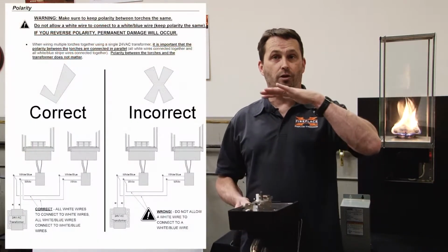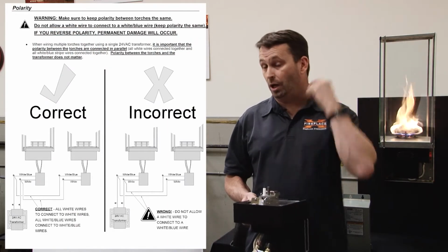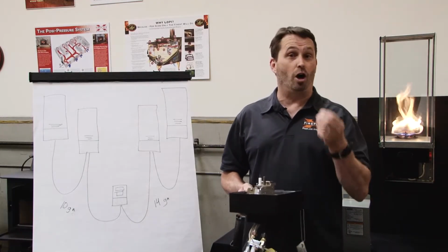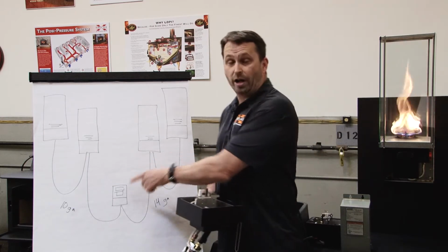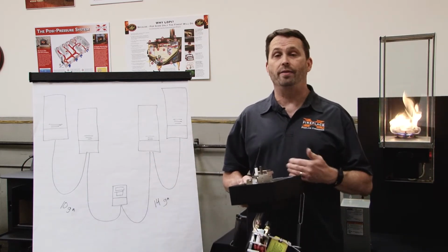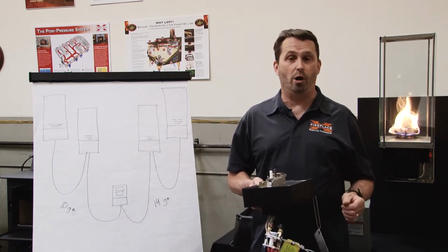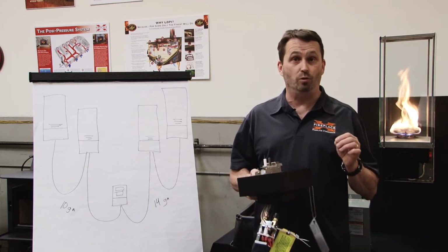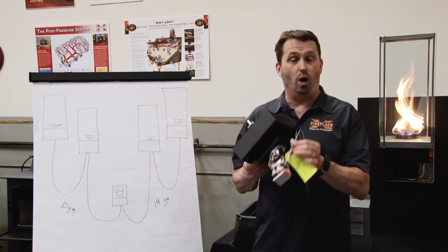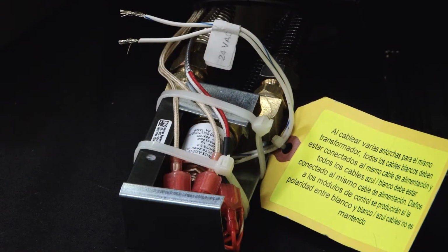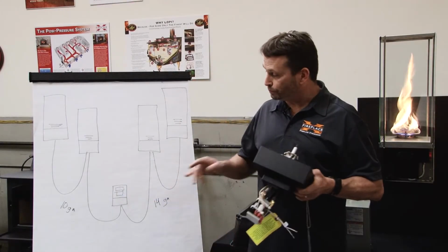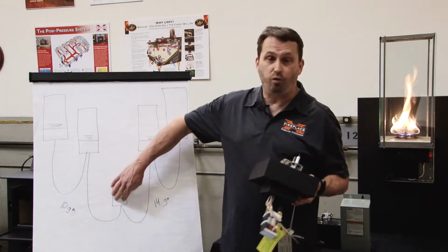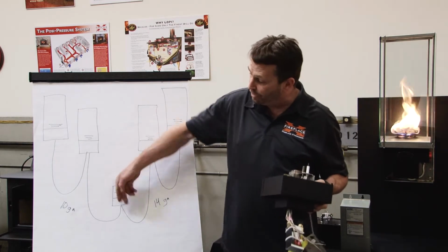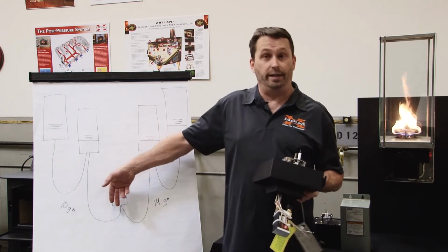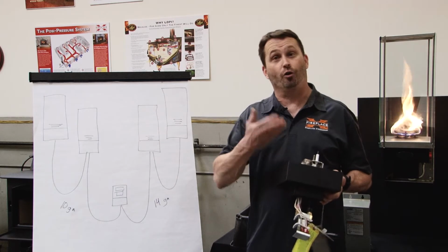There's a full page warning in your manual about the polarity. The polarity is also mentioned in the transformer instructions. So we put it in there everywhere we talked about wiring of the torch, and it is absolutely critical that when you're wiring the torches, the white wire and the white blue wire do not get connected to each other. So when you connect to the transformers, because it's an AC circuit, it doesn't matter which way they get connected to the transformer as long as they're all the same.